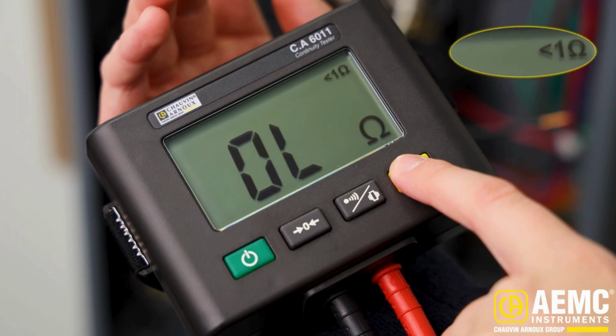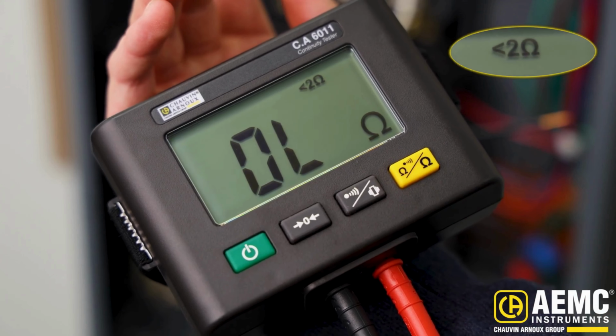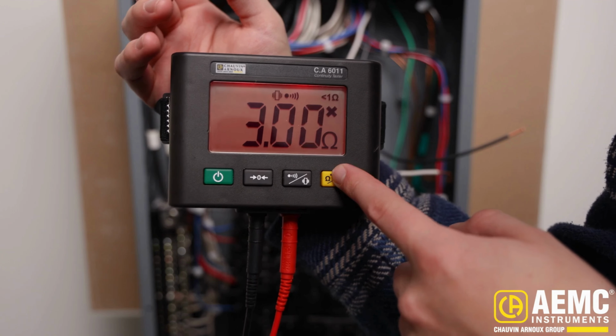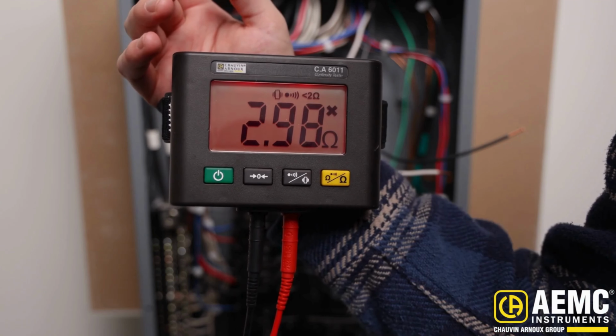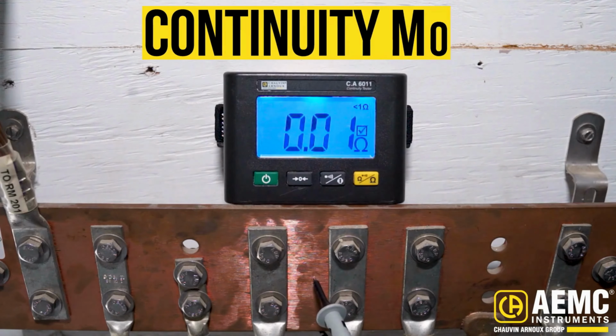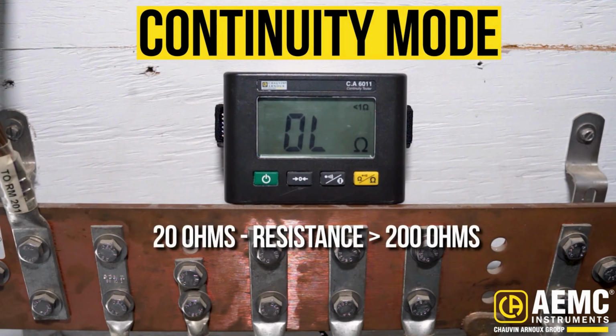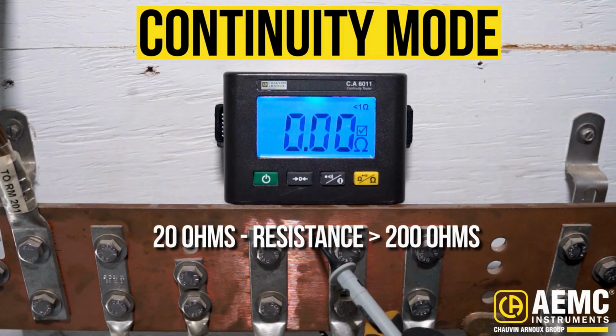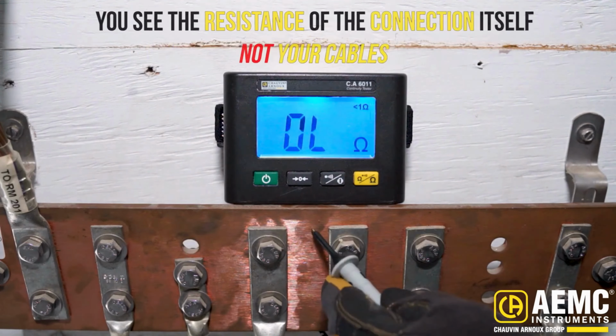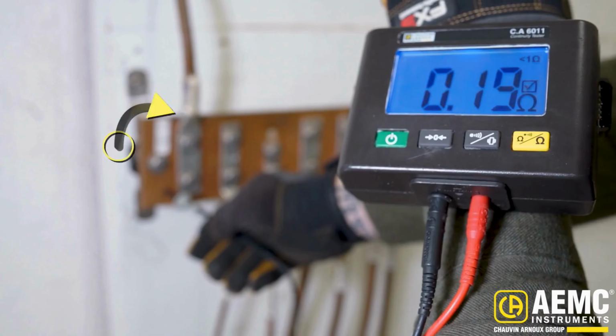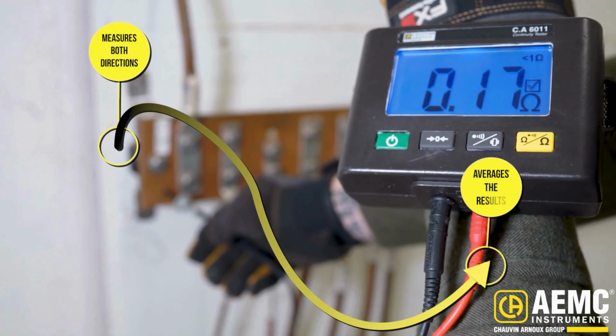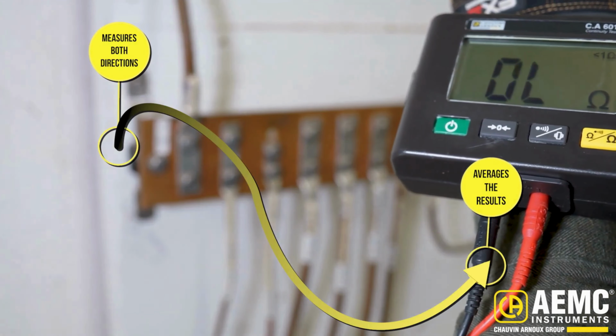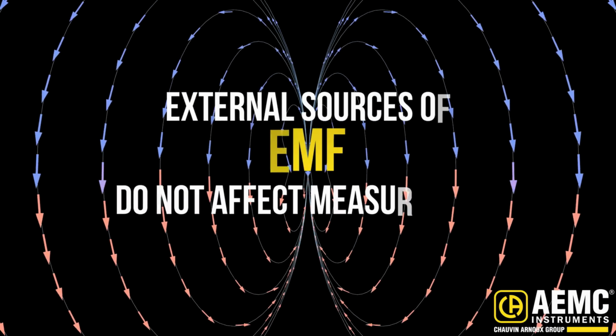You can set the CA6011 to use a 1 ohm or 2 ohm continuity threshold, helping align your pass-fail criteria with the safety standards or site requirements you're working under. In continuity mode, the lead compensation function automatically subtracts resistance of your test leads, resulting in more accurate readings. What you see is the resistance of the connection itself, not your cables. Continuity tests are driven with a 200 mA test current and automatic polarity reversal. That means it measures in both directions and averages the results, giving you stable, repeatable readings on low resistance paths. This also ensures external sources of EMF do not influence the measurement results.